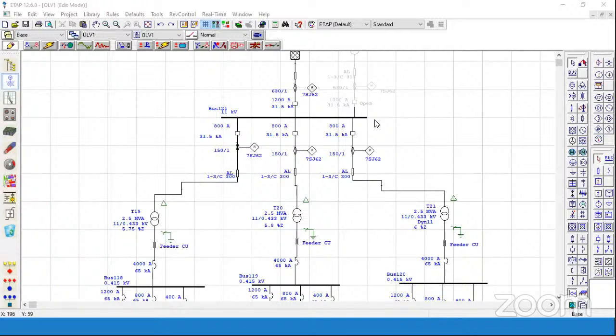Just before going ahead, let me familiarize you with ETAP. ETAP is a simulation study software having a vast library of numerical relays and circuit breakers of different manufacturers like Siemens, ABB, Schneider, GE, Alstom. It has existing numerical as well as electromechanical relays, so that we can check the parameters and the coordination of the entire network. ETAP is also helpful to evaluate short circuit as well as load flow studies of our network.